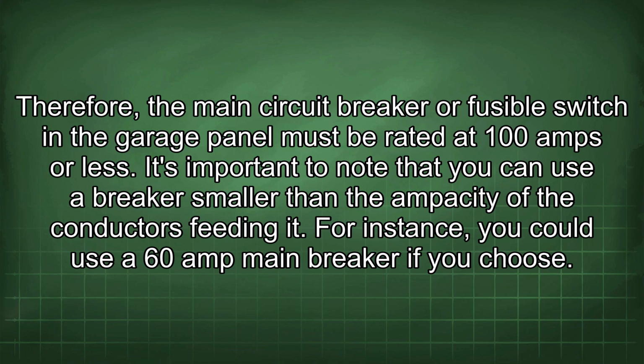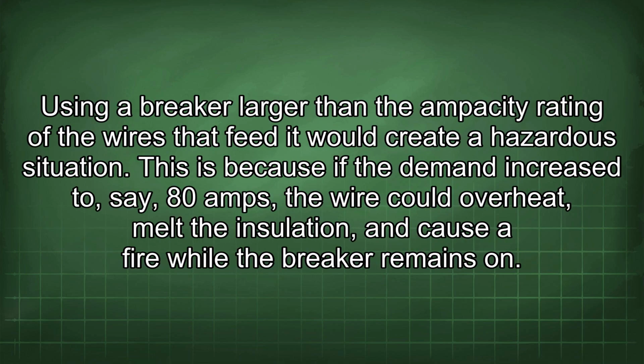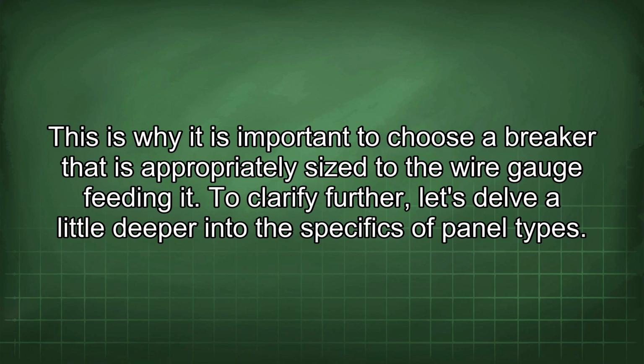It's important to note that you can use a breaker smaller than the ampacity of the conductors feeding it. For instance, you could use a 60-amp main breaker if you choose. Using a breaker larger than the ampacity rating of the wires that feed it would create a hazardous situation. This is because if the demand increased to, say, 80 amps, the wire could overheat, melt the insulation, and cause a fire while the breaker remains on. This is why it is important to choose a breaker that is appropriately sized to the wire gauge feeding it.